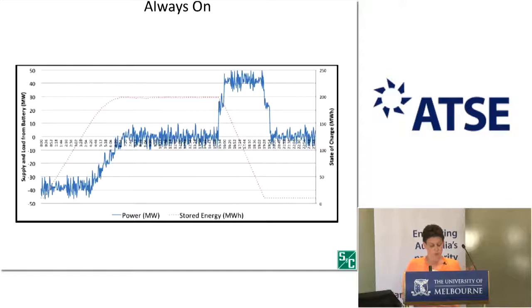So what we have here is a 50 megawatt battery operating in what's described as an always-on model. It's providing dynamic frequency response, shown as the blue line going up and down, and underneath you can see a red dotted line, which is the battery recharging. Then in the evening it provides capacity, supplying energy to support demand, and that's when the battery is discharging. So a battery can operate somewhere in its range - as long as it's got enough room to go up and down, it can provide frequency response.